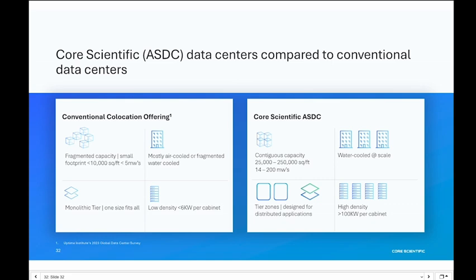We're designing for water cooled at scale—every single cabinet in our data centers, all 200 megawatts for CoreWeave, will be water cooled. Our tiering approach is highly optimized, allowing us to build faster at lower cost and get GPUs to market quicker. Our densities are designed above 100 kW a rack, and likely future iterations will go much higher, as we future-proof high-performance computing at scale as part of our design.